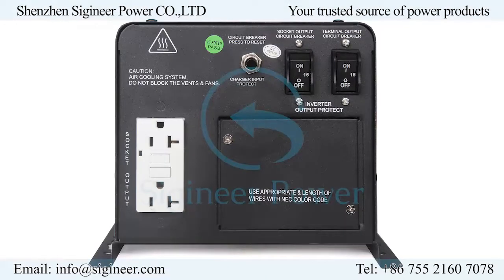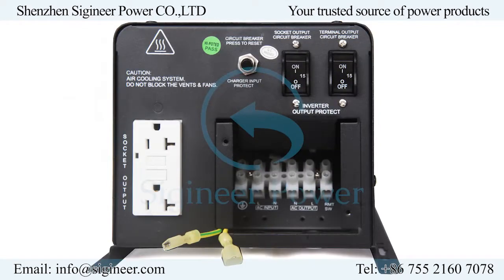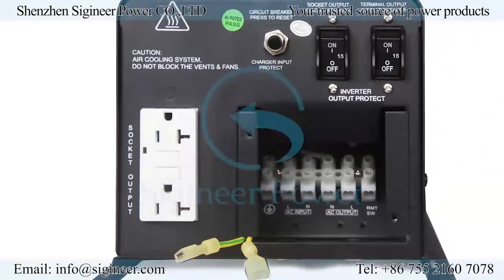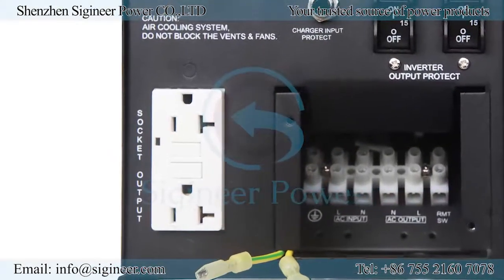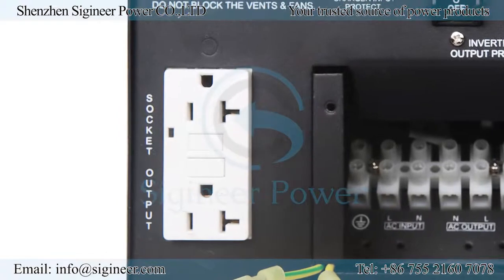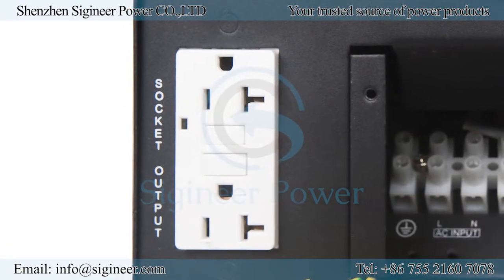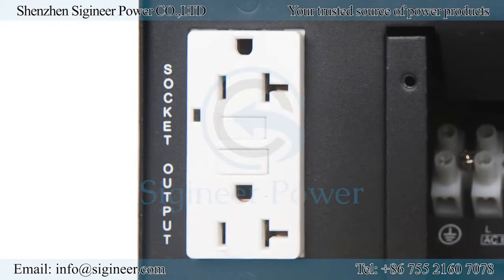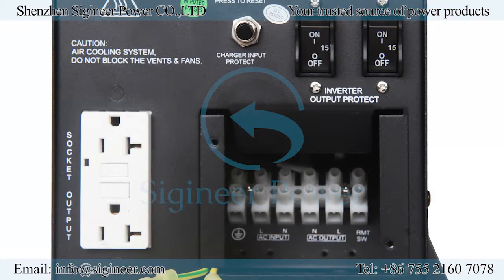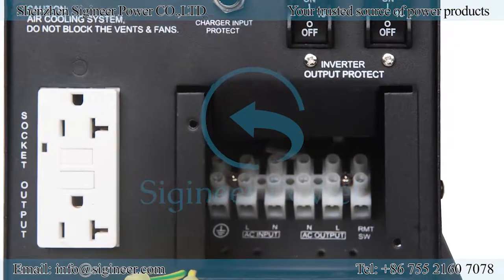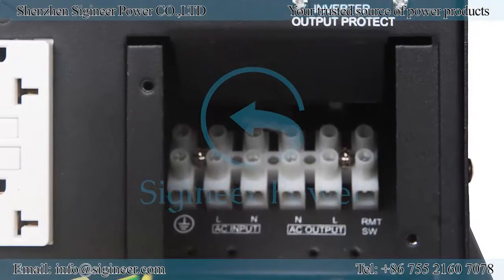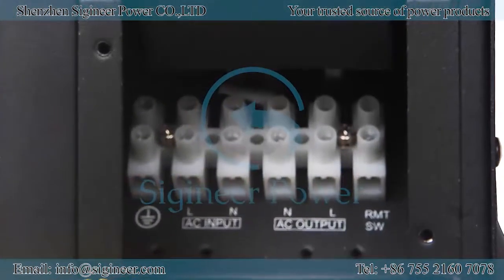With the AC Direct Connect terminal block, you can hardwire your AC input and output. This inverter charger features an AC wiring compartment with 2 strain relief connectors to access the AC input and output terminal block. This is where you hardwire your AC input and output. On the left side of the AC wiring compartment, there is a resettable GFCI outlet for plugging in 120 volt AC devices to the inverter. The 12V DC remote on-off switch function is available on this inverter. This makes the inverter also manageable from a 12-volt DC source.